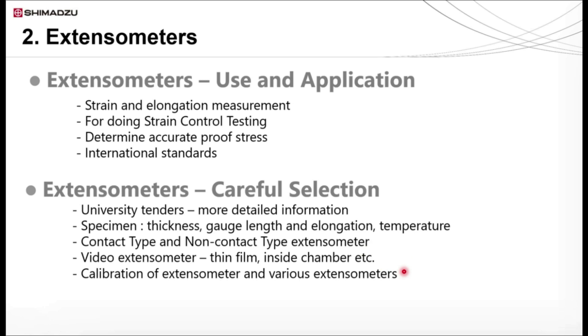So careful selection of extensometer will help you to save money, especially in tenders, university tenders. I recommend all end users to give more detailed information. Be well aware of your specimen thickness, gauge length, elongation, temperature requirement, etc. Extensometers are broadly classified into contact type and non-contact type, which I will talk about in detail in the next slide. Video extensometer can be used in areas where conventional contact type extensometers have practical difficulty. Extensometer may also require yearly calibration, so if this is required, inform the supplier in advance.